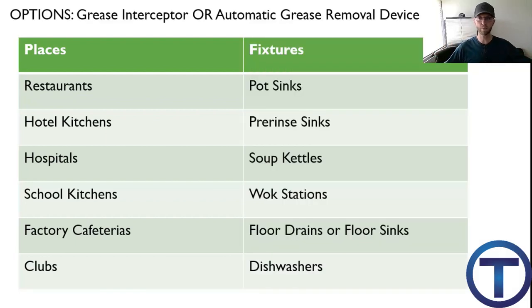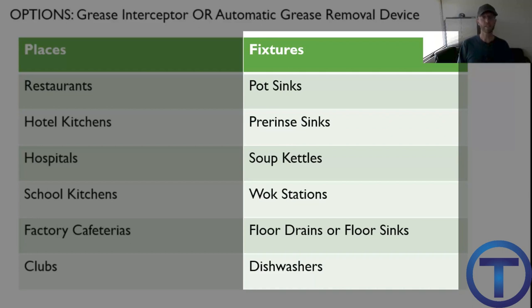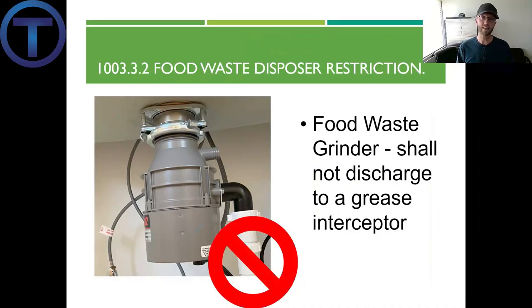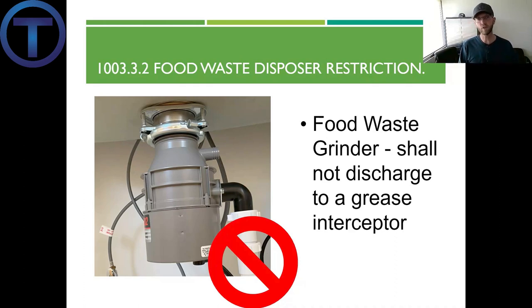Some fixtures required to go through a grease interceptor or automatic grease removal device include pot sinks, pre-rinse sinks, soup kettles, wok stations, floor sinks and floor drains, and dishwashers. Section 1003.3.2 states that food waste disposers, or garbage disposals, shall not discharge into a grease interceptor. The reason is not that they don't have grease — they do — but because they output so much liquefied food waste, it would make a total mess and inhibit the grease interceptor's ability to separate grease from that ground-up food.